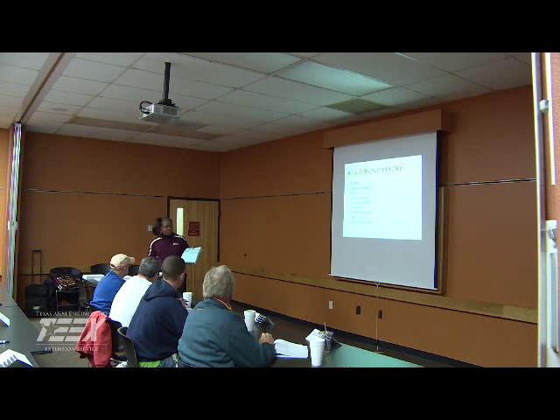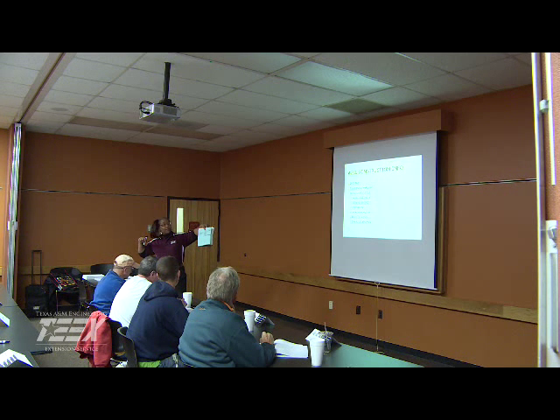So gallons per minute, divided by feet? No, times feet of head, divided by 3960, times PE times ME, which is pump efficiency, motor efficiency.